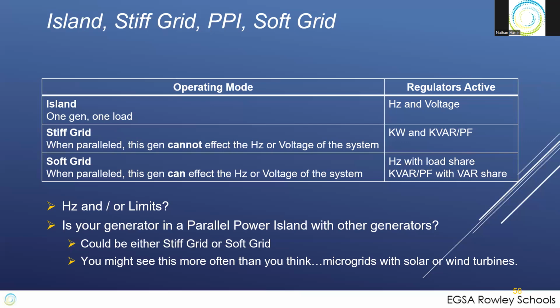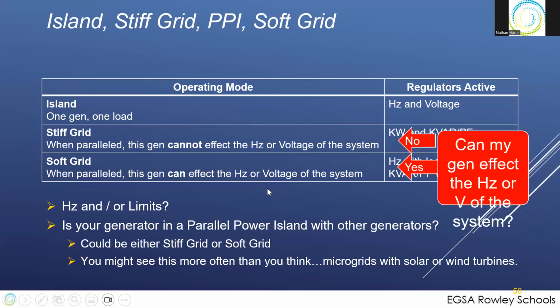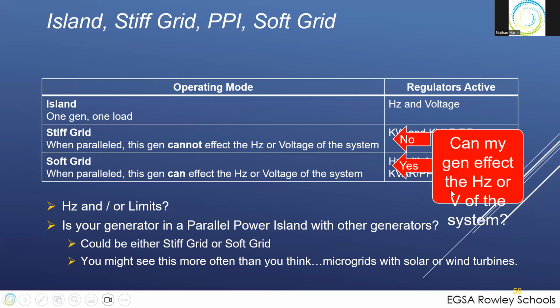So it took about a week to get all these little generators back up again. Nothing happens fast in the islands, and they brought the system back up again because it was a stiff grid. It was actually on a soft grid. So make sure your control system is set up with the right information. And that is, if your generator can affect the voltage or frequency of the system, it depends if it's a soft grid or a stiff grid, right?